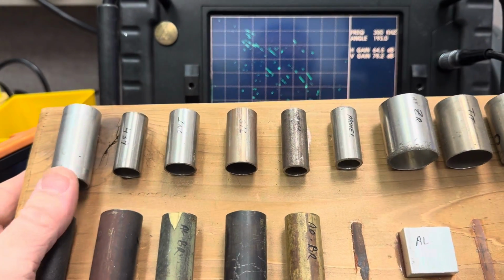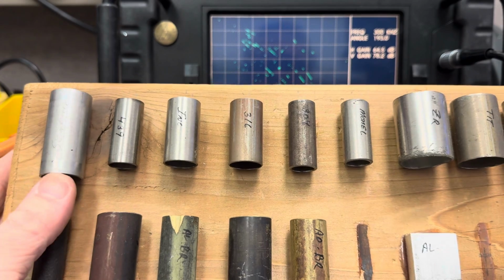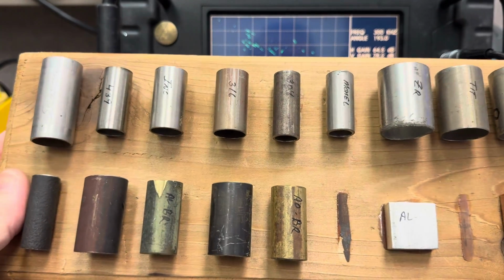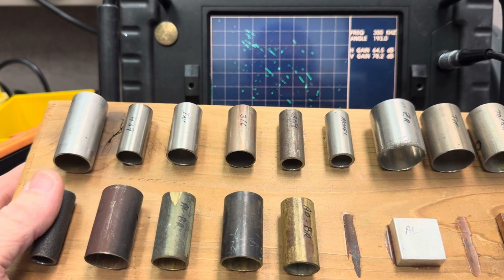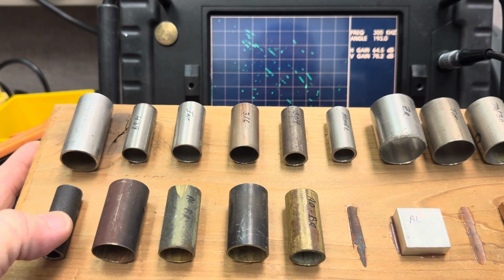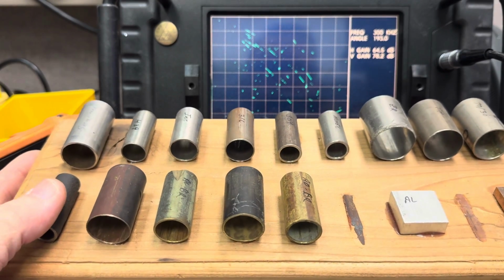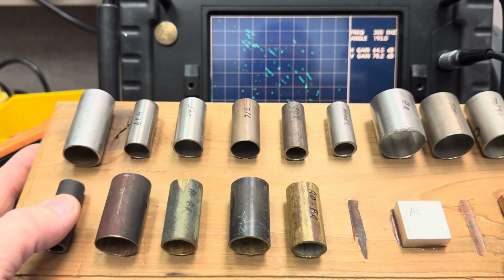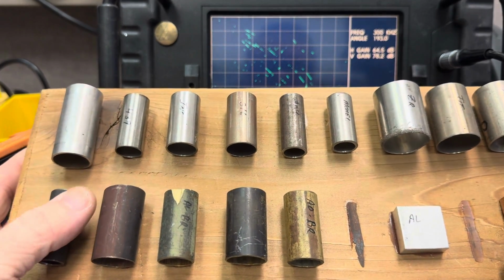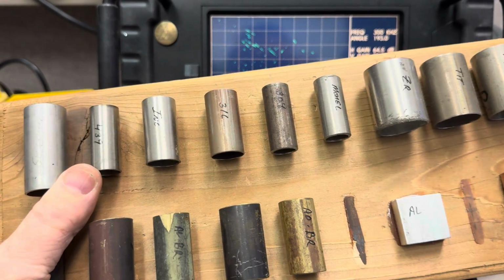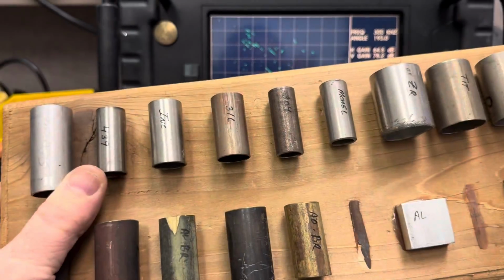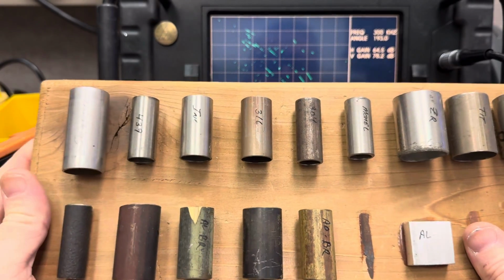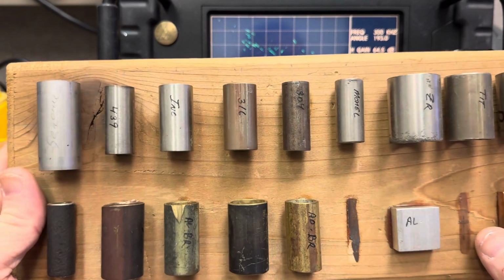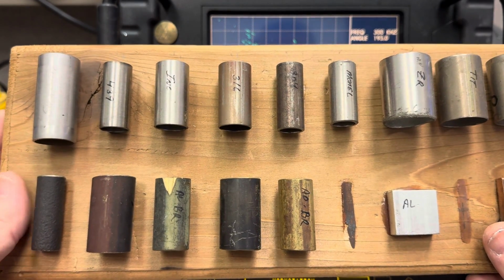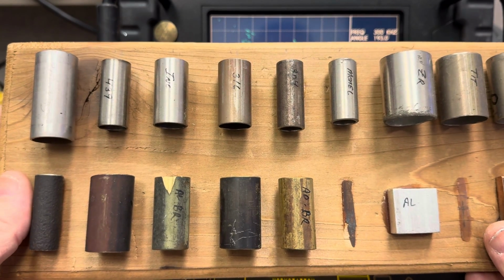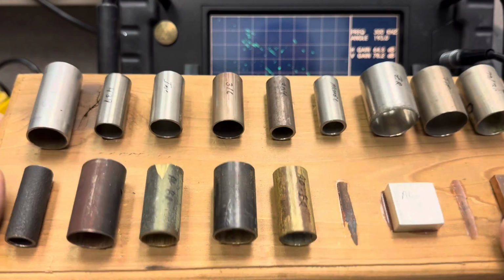Now, because I have a lot of different tubing that I deal with, and they've been inspected for years, the test procedures are already set up. But, and this is important, they're legacy procedures. So I don't know how they chose the frequencies. So what I'll do is I'll check them. And I usually use the slide rule because that's a real quick and easy way to check for the F90 frequency. And then once you use a slide rule to calculate F90, you just double it for your prime frequency, which is your highest frequency. F90 is your optimum detection frequency.